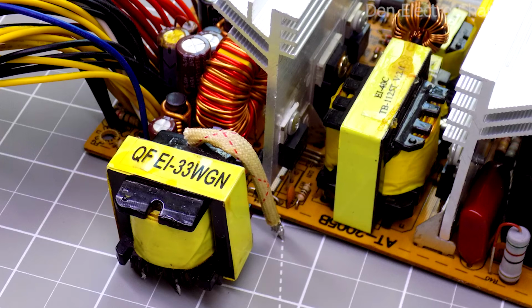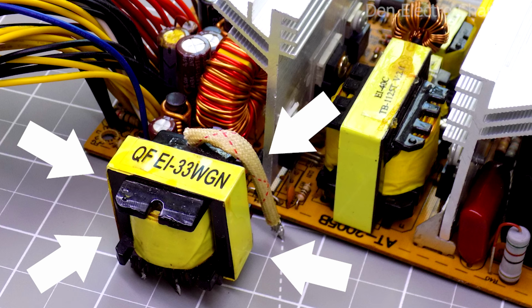Even though the transformers look almost identical, the operating frequency of their power supplies may be different. If the frequency of this power supply is significantly higher than the frequency at which this transformer was operating, it may heat up even at idle.